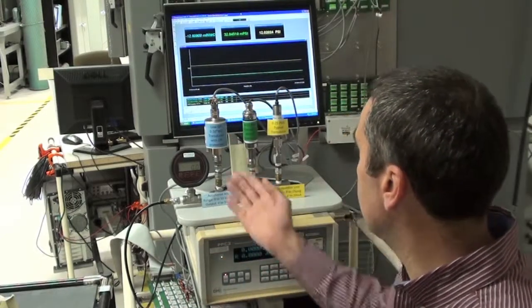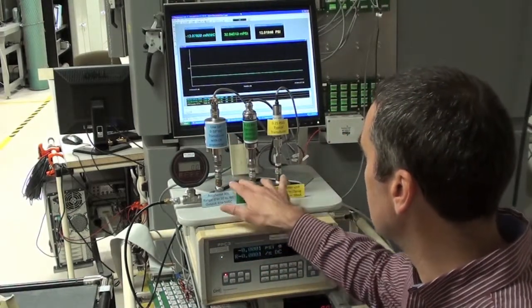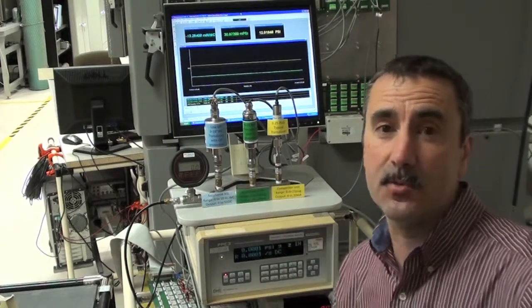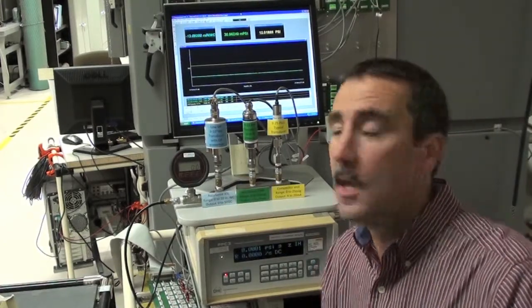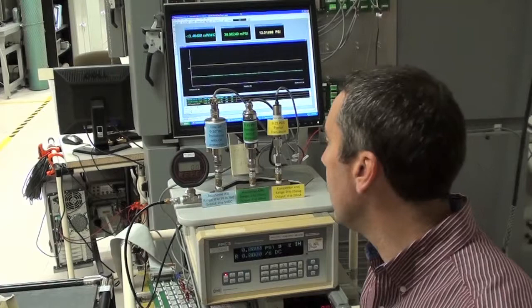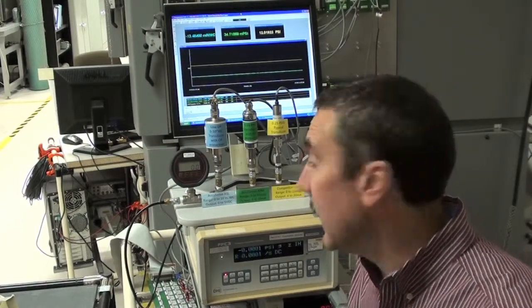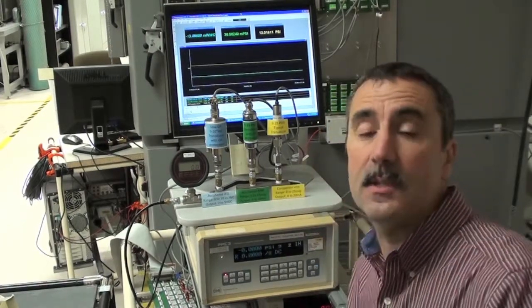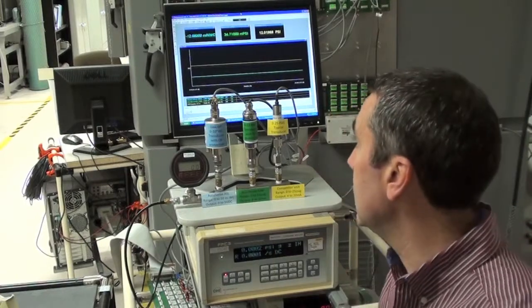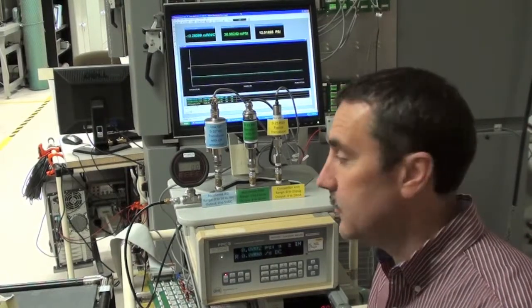I'm a manager of R&D here at Setra, and I'm here to talk to you about high overpressure capability on pressure transducers. Behind me, you will see there are 3 pressure transducers installed in a manifold. I'll be giving a demonstration of overpressure capability. 2 of these transducers have high overpressure protection, and one of them is a typical transducer that does not. So you will see the benefit of this feature.